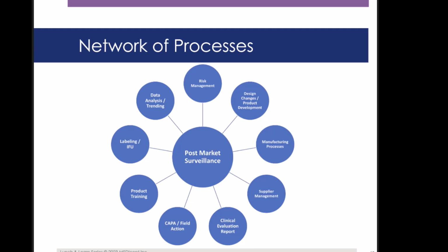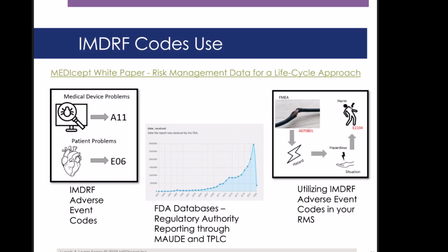Gathering and properly using real-world data to initiate actions and make changes is vital to an effective post-market surveillance process. The more information that you put to use, the greater benefit that you'll receive from the process. You can also improve the efficiency of the post-market surveillance process through the use of a coding system for identifying and tracking detected issues throughout your QMS.